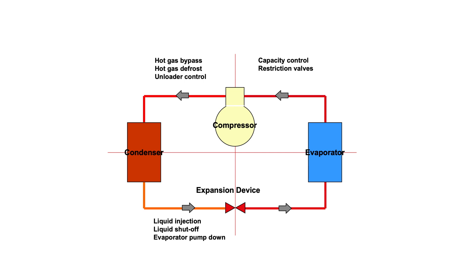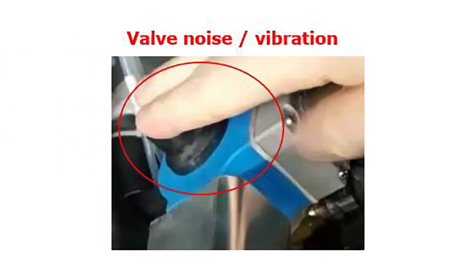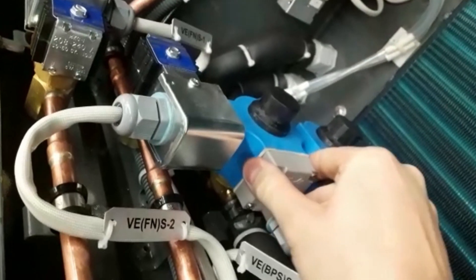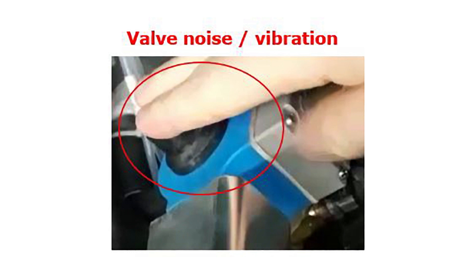The typical solenoid valve locations and functions are shown in this principle diagram of a refrigeration system. Valve noise and vibration are identified in the same way no matter where the valve is located in the system. Here you can see an example of such failures. You will normally hear and or feel by hand such valve failures.